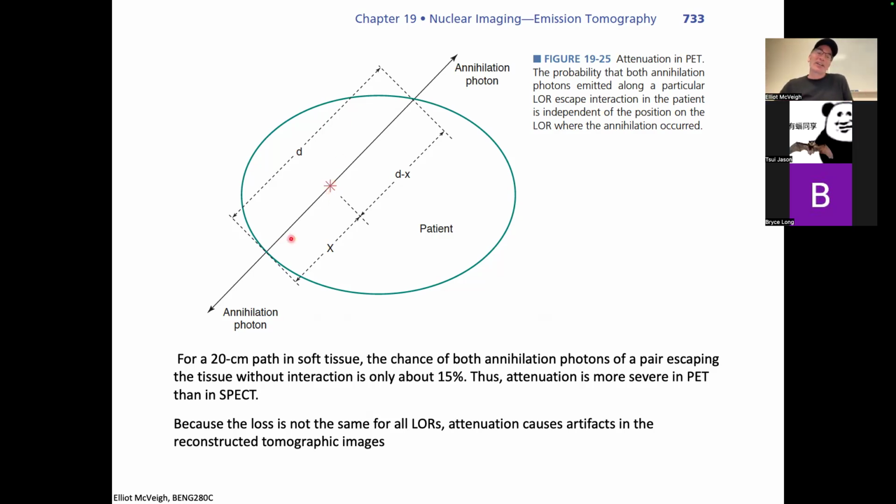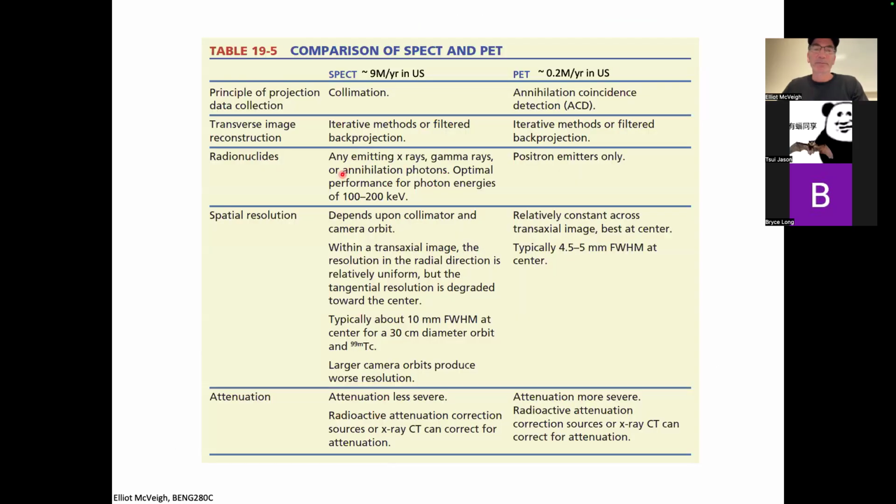So basically you've got high probability, low probability, 50-50 probability in the middle, and that's your probability all the way along the line. So you don't have to worry about this depth-dependent probability of getting a coincident event. They just self-normalize that way because it's these two photons. So it's like a self-normalizing depth compensation.